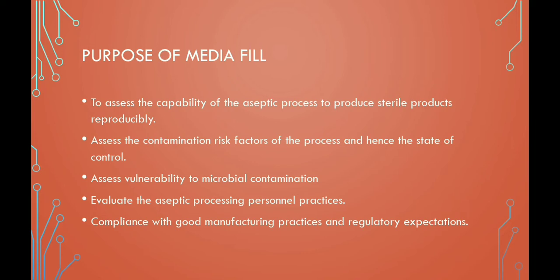The purpose of media fills is to assess the capability of the aseptic process to produce sterile products and reproducibility, assess the contamination risk factors of the process and the state of control, and assess the vulnerability to microbial contamination. Media fills also demonstrate that aseptic operating practices and procedures are appropriate, evaluate aseptic processing personnel practices, and are used to qualify, re-qualify, or disqualify personnel. They also ensure compliance with good manufacturing practices and regulatory expectations.